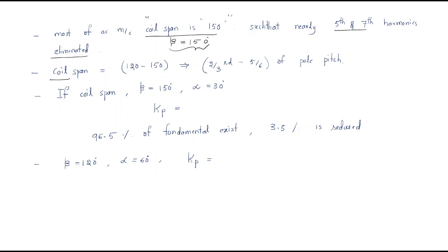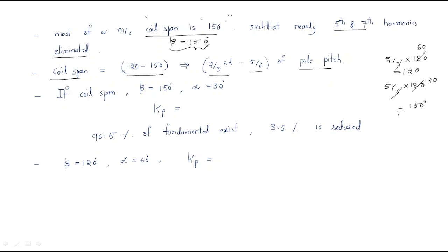Generally, coil span is between 120 degrees and 150 degrees. That is, two-thirds of the pole pitch — which is two-thirds of 180 degrees — giving 120 degrees, and five-sixths of the pole pitch — five-sixths of 180 degrees — giving 150 degrees. So coil span ranges from two-thirds to five-sixths of the pole pitch.